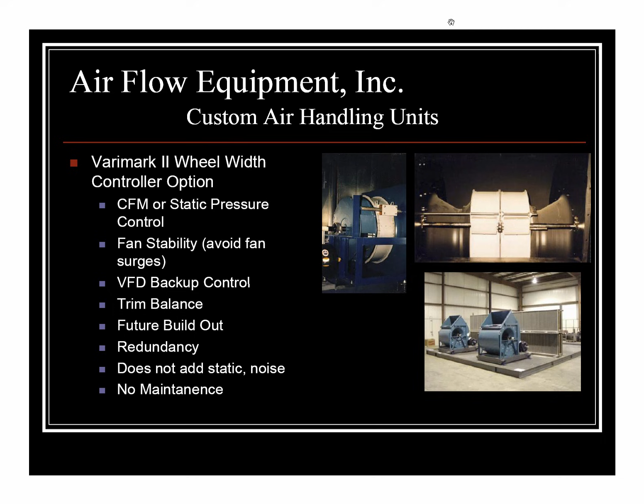It can be used also in a situation, like I said, with a future build-out. We've used it in that case. Again, where you've got a future larger load, you cover up part of the wheel, reduce the CFM, and then as the additional space comes online, you can move this out of the way going to full flow. So it's kind of a neat device that can be used in conjunction with a VFD as kind of a backup control, if you will. So even if something goes wrong with the VFD, you can still use the wheel width controller to maintain control of the system.